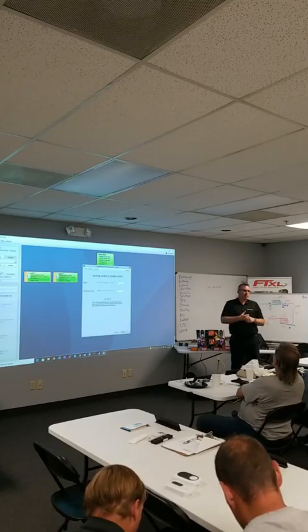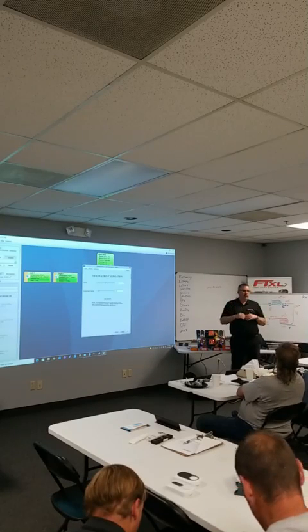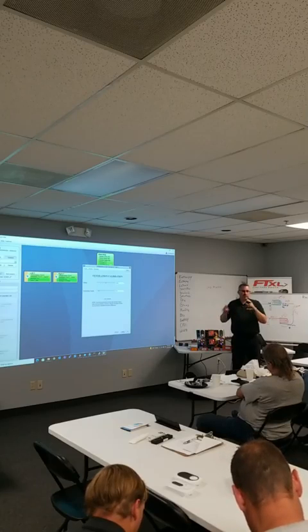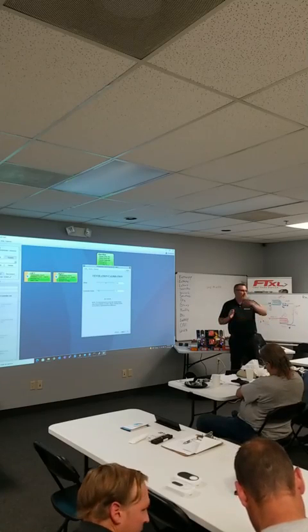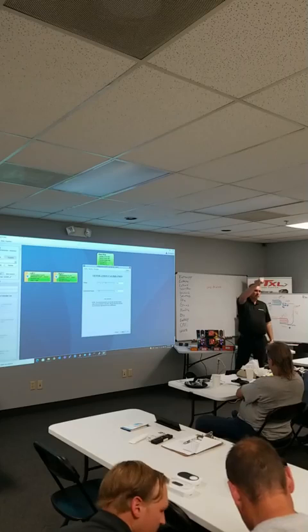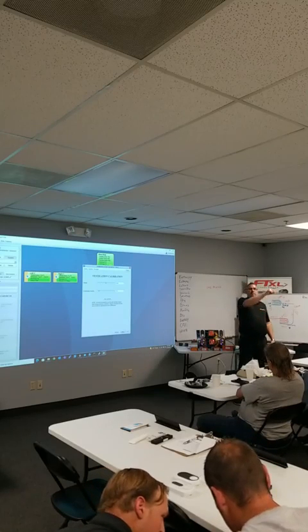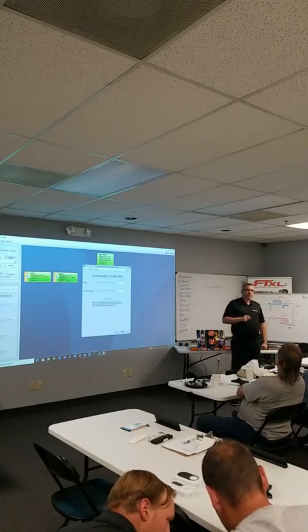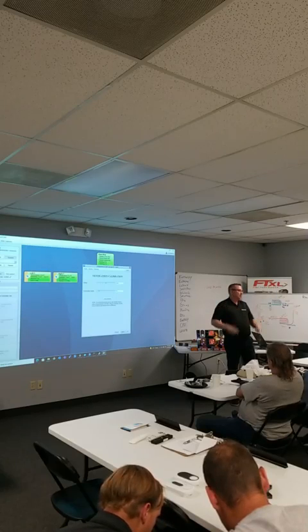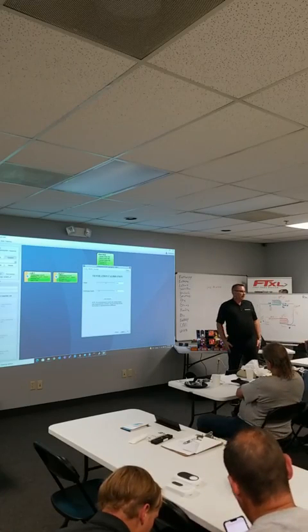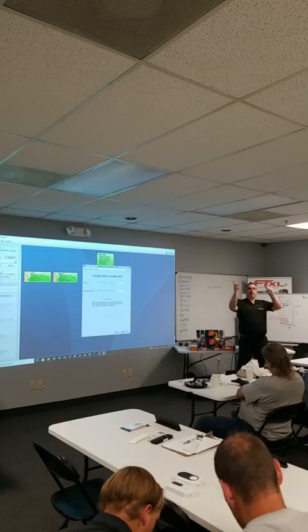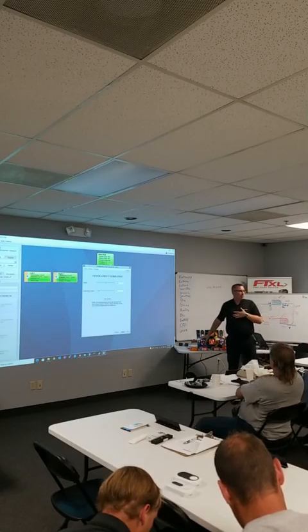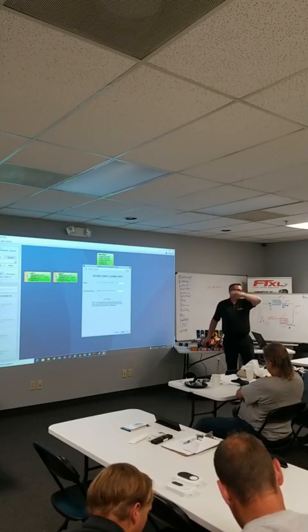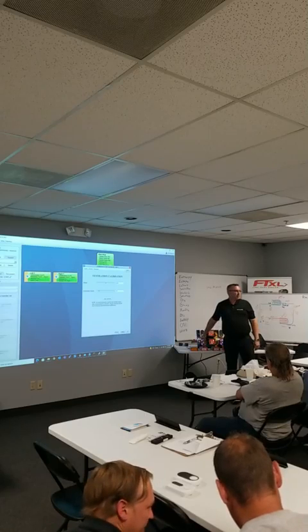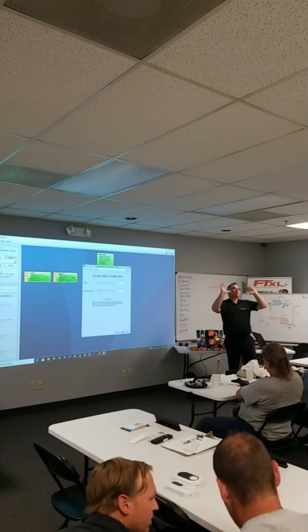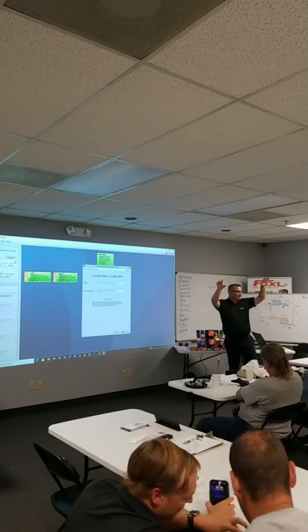And they may say, put it to your high CFM, and they'll go read it. Yeah, that's the calibration, or that's the test part. The balance part is really them going back to each of the manual dampers. If it says there's 4 diffusers and it should be 100 CFM in each one, and these two have 50 and those two have 150, well, yeah, we've got the right CFM total, but not here, and that has nothing to do with me. We've already read that, okay, the PROLON system's reading 400 CFM, I got 400 CFM. Their job is then to go back and balance the diffusers.